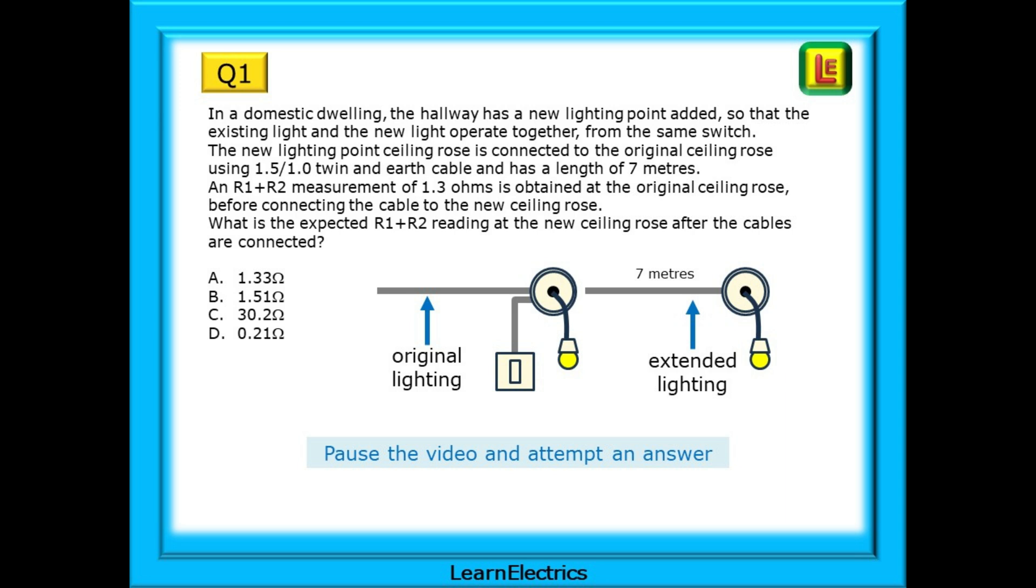In a domestic dwelling, the hallway has a new lighting point added, so that the existing light and the new light operate together from the same switch. The new lighting point ceiling rose is connected to the original ceiling rose using 1.5 by 1 mm twin and earth cable, and has a length of 7 meters. An R1 plus R2 measurement of 1.3 ohms is obtained at the original ceiling rose, before connecting the cable to the new ceiling rose. What is the expected R1 plus R2 reading at the new ceiling rose after the cables are connected?